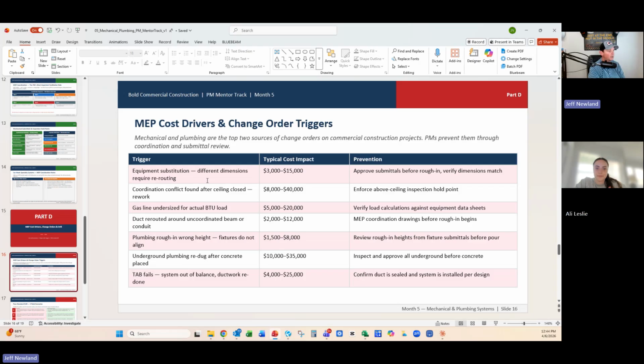Coordination conflict found after the ceiling is closed in, yeah, that sucks. Gas line undersized for the actual BTU, that would typically be caused because they changed pieces of equipment out and nobody let the gas company know. Duct rerouted around an uncoordinated beam or conduit, that's where we talked about the electrician running his conduits and then they're right in the way of everybody else.